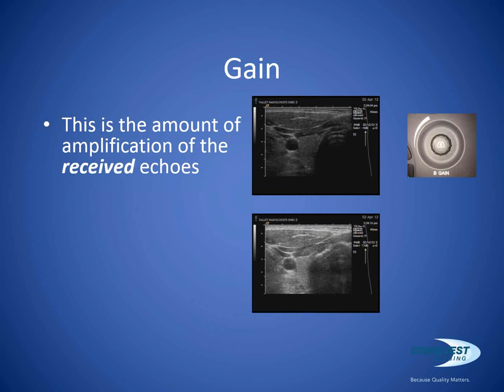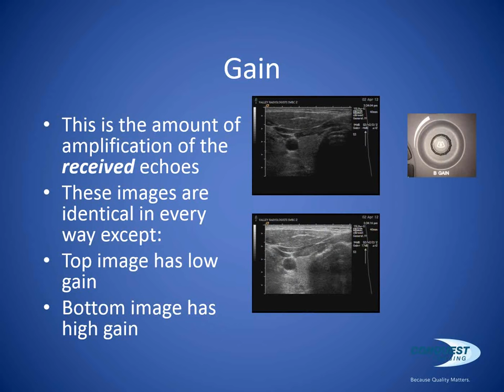These are the received echoes, and with this B gain, or this overall gain, you're telling the machine how much to amplify those received echoes. These images that you're seeing here, what you're looking at here is my thyroid, top and bottom, and there is no difference in those two images other than I've increased the gain in the bottom image. You can see in the top image my gain is, I believe, minus 4 decibels, and in the lower image I've increased the gain to 17 decibels.